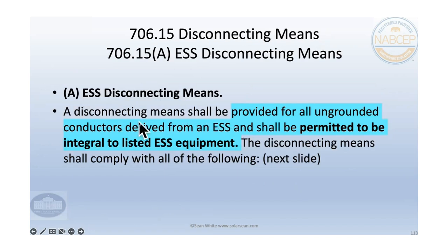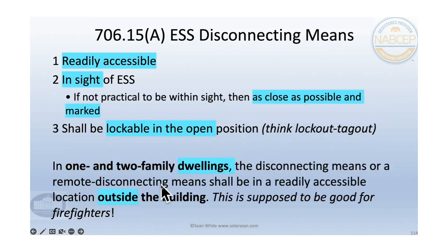Let's see, disconnecting means shall be provided for all ungrounded conductors derived from an energy storage system and shall be permitted to be inside of the energy storage system. So let's kind of look over here. The disconnecting means needs to be readily accessible in sight of the energy storage system and shall be lockable in the open position.